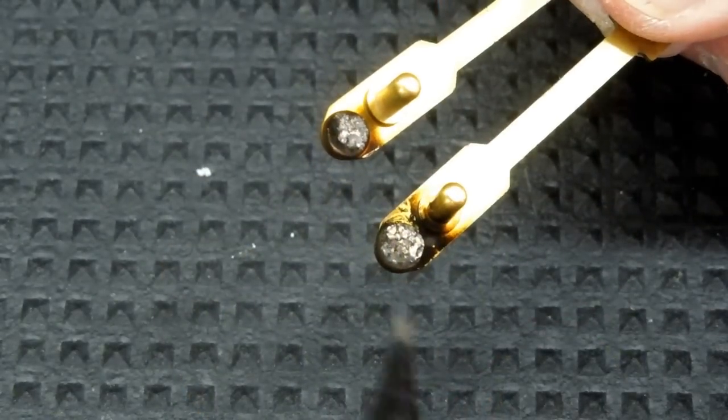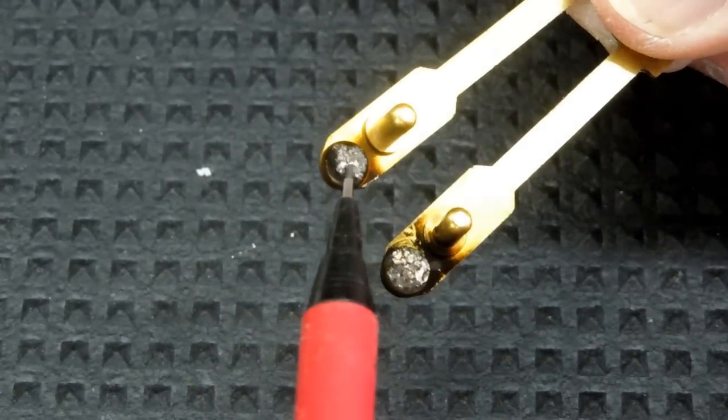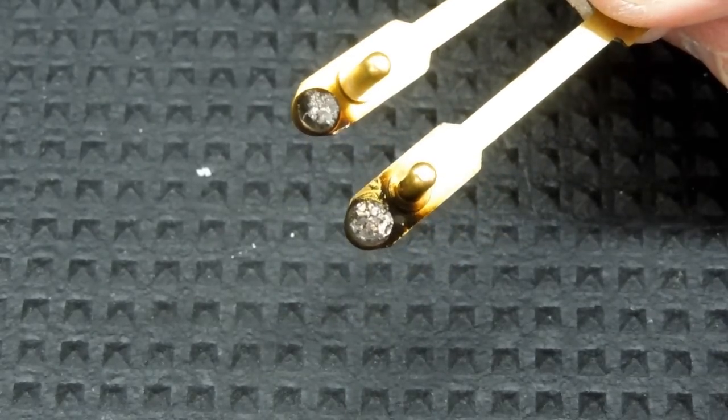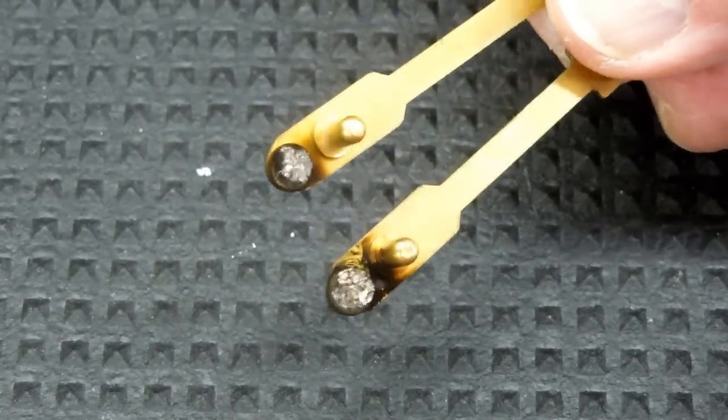I pulled the contact arms out and you can see these are very burnt and deeply pitted. So that's the main reason for the failure. The fact that the wires were about to fall off was a secondary issue.